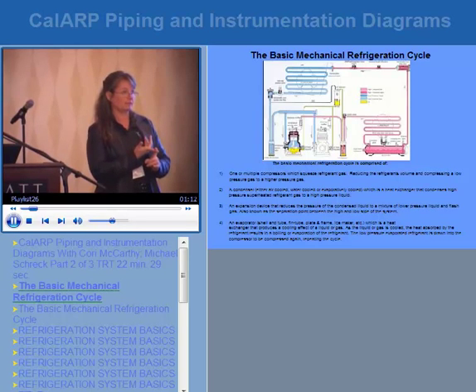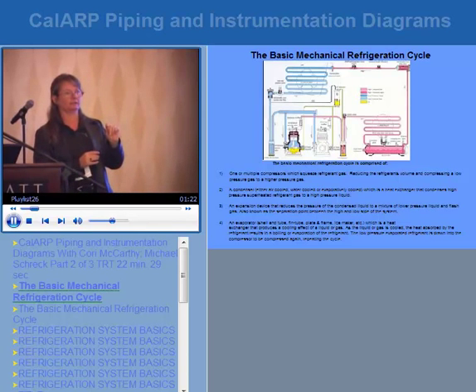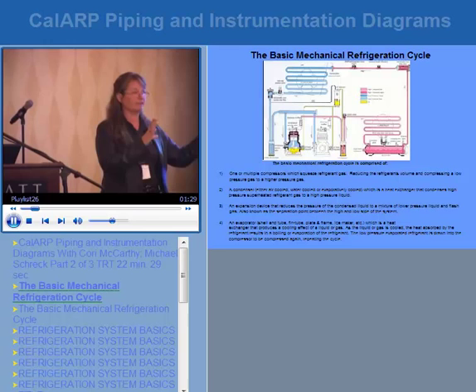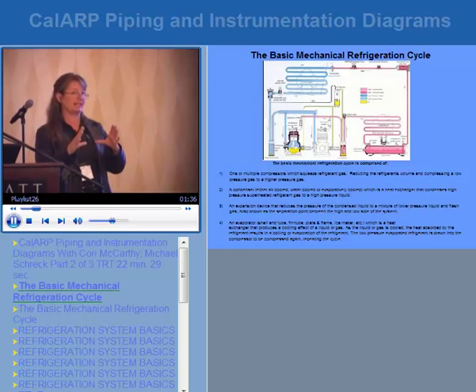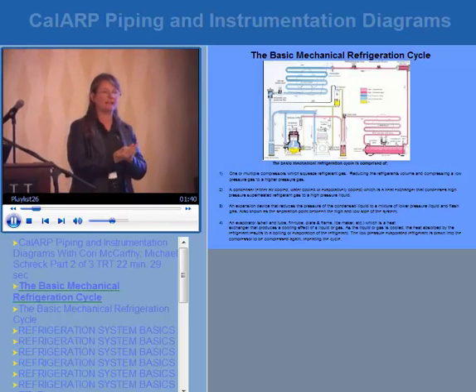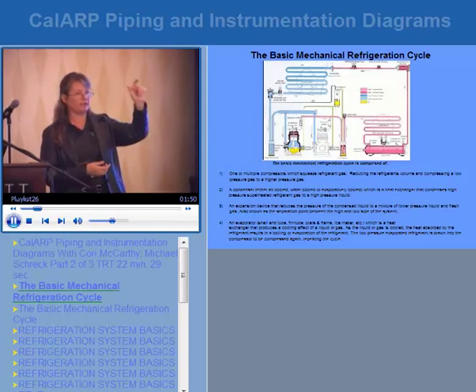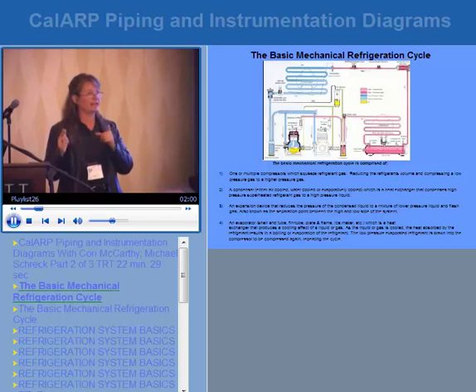Make a list of the major components from the drawings. For example, count compressors on the drawing — look for statements like 'for future use,' which may indicate planned expansion. If you walk the plant and count six compressors but only five are on the drawing, and the drawing shows 'for future use' where the sixth now stands, they've installed it without updating the drawings.